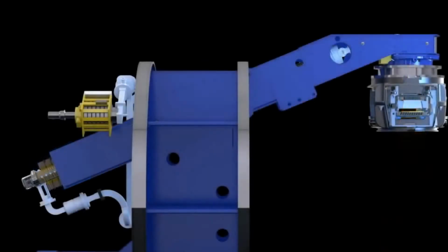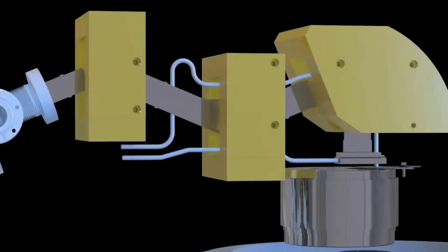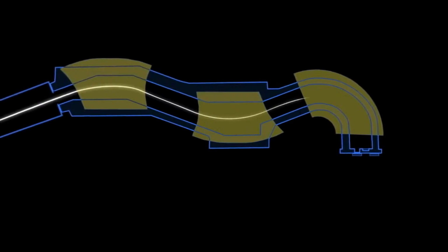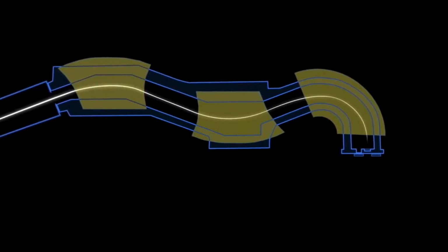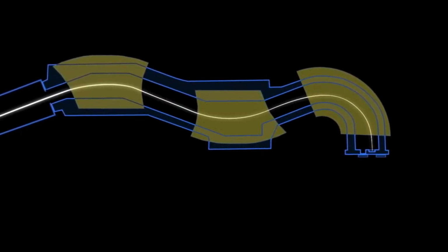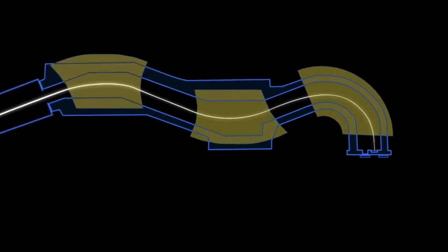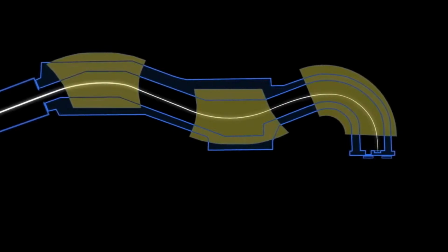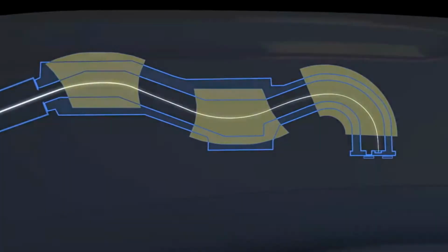The electrons exit the waveguide and enter the flight tube, where the beam is redirected towards the target. The electrons travel along a slalom path within the flight tube. 3 pairs of magnets on either side of the flight tube cause the electron beam to bend through the turns of the slalom. This process not only positions the beam to strike the target, but it also further focuses the beam to a diameter of 1 millimeter. The design of the magnets enables them to focus electrons of slightly different energies onto the same point on the target. This is called achromatic behavior.